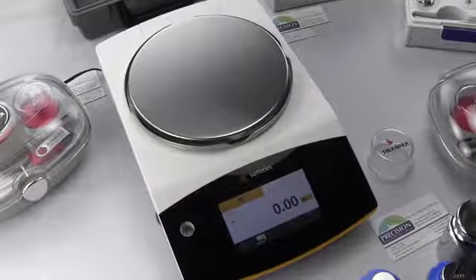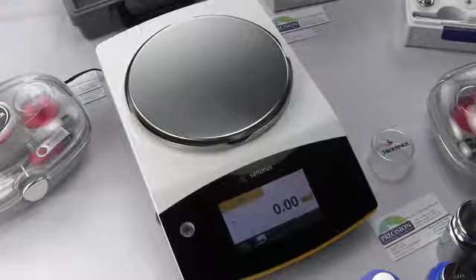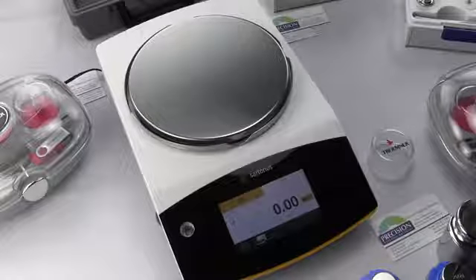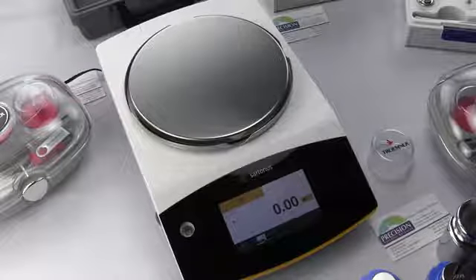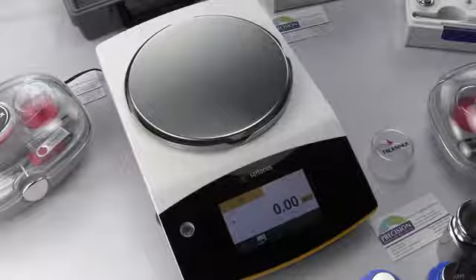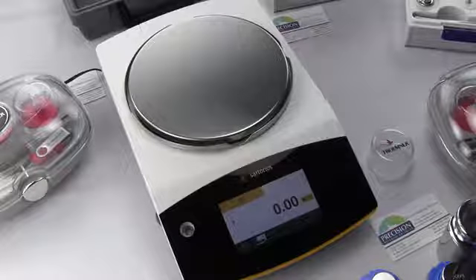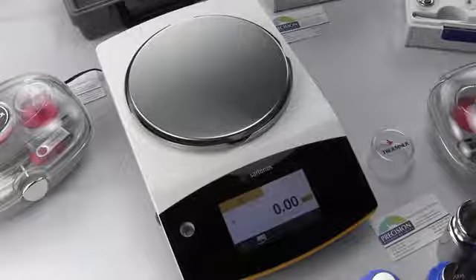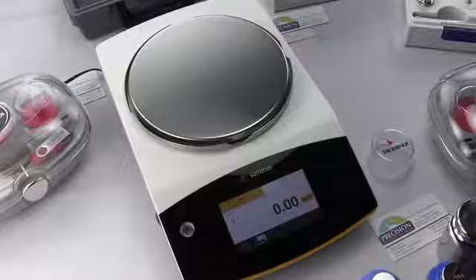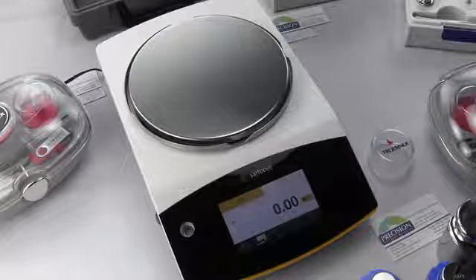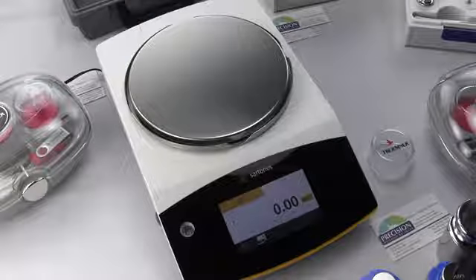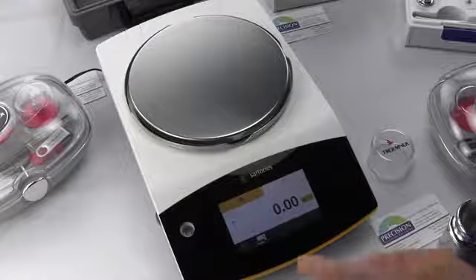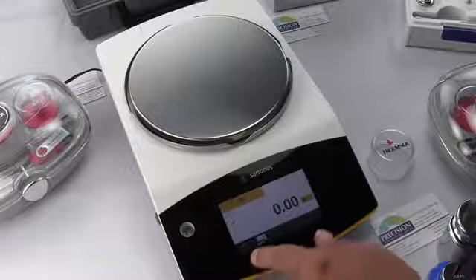So now let's perform an external calibration. On external calibration, this procedure will be similar for all three of the series, the Practum, Quintix, and Secura. For external cal, you'll need an external weight, and this is an optional accessory. Again, we want to make sure that the weigh-in pan is empty and we have no breezes. We're in a stable environment.